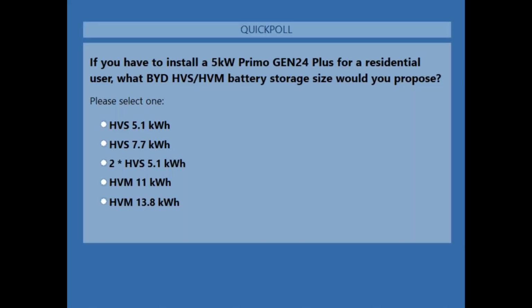So the question is, if you have to install a 5 kilowatt Primo Gen24 Plus for a residential user, what BYD HVS or HVM battery storage system would you propose? You could propose the HVS 5.1 kilowatt hours. You could propose the HVS 7.7 kilowatt hour battery. You could propose two HVS 5.1 kilowatt hour batteries. If you do that option, you're going to be left with about 10.2 kilowatt hour storage. Or the fourth option is that you could propose the HVM 11 kilowatt hour. And the last option is that you could propose the HVM 13.8 kilowatt hour battery.